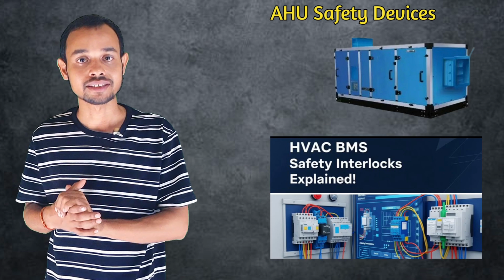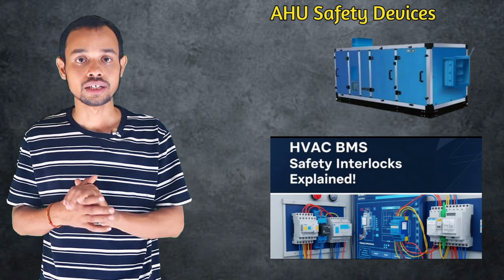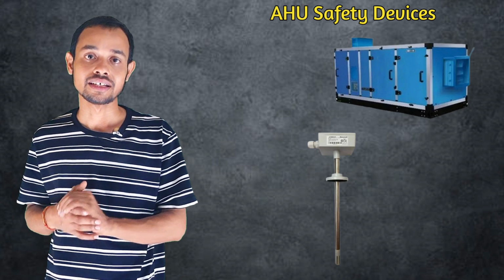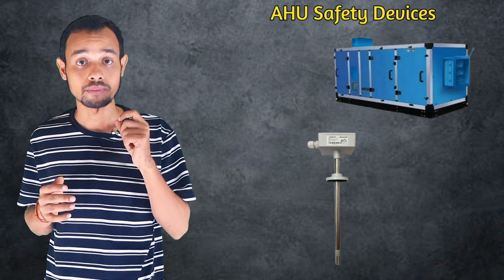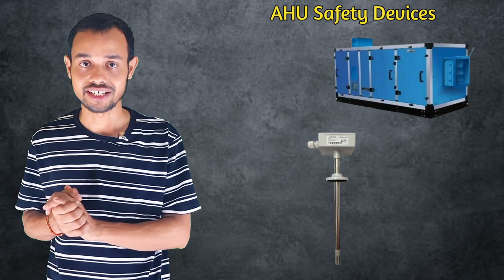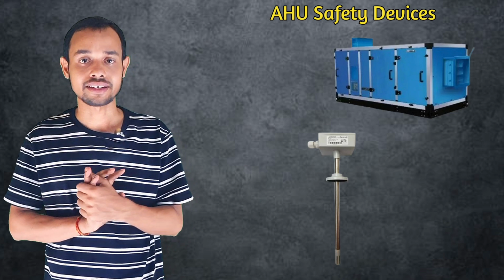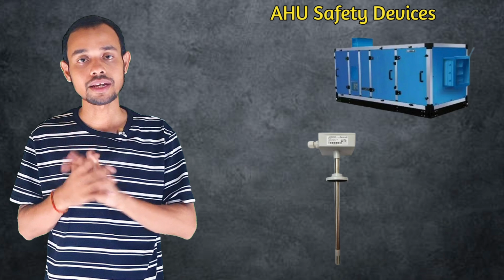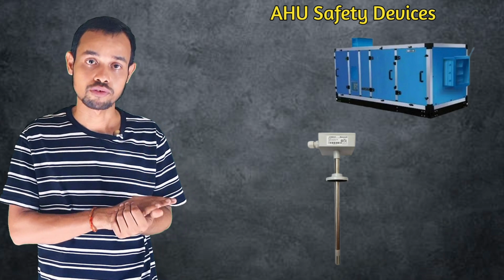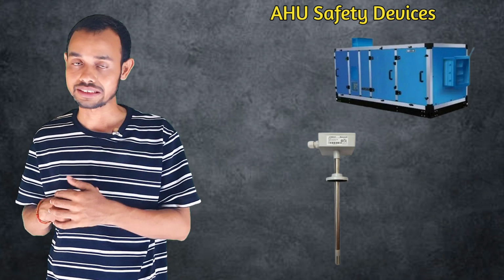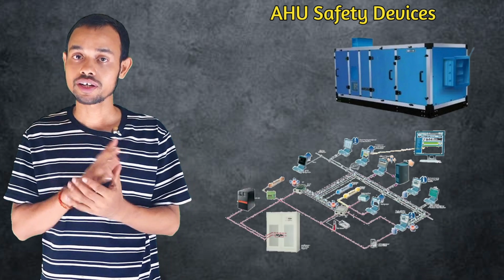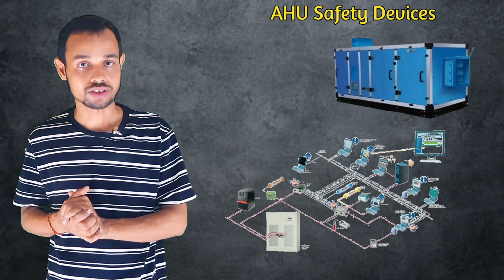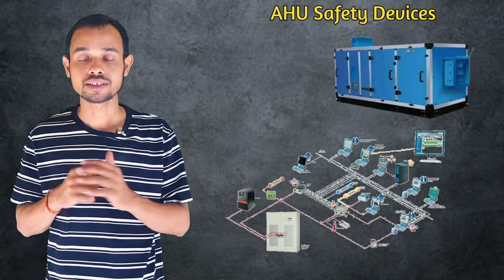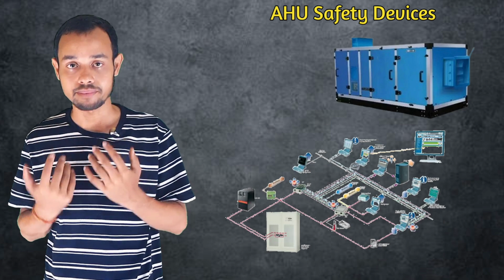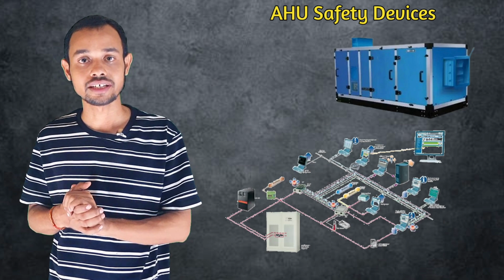Okay, now the monitoring devices which check the health of the AHU: the temperature and humidity sensor, to maintain comfort and energy efficiency. Then the supply and return air sensor. What is the supply and return sensor? It monitors the real-time performance of the system through supply and return air temperature. And next is BMS integration. What is BMS integration? Modern AHUs are connected to the building management system, BMS, so that faults can be remotely detected and managed.